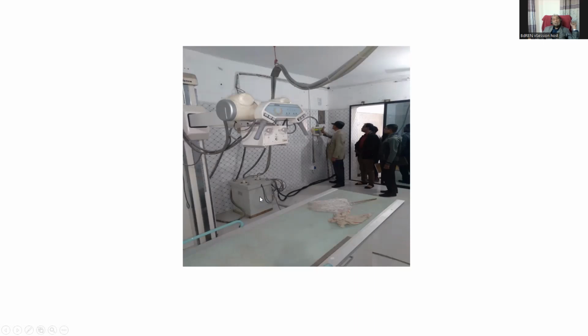For the performance of the X-ray, in this stand there is oil, an iron core, and several sophisticated components have been used. So it is known as the X-ray generator. Basically, it is a copper transformer. It transforms low voltage to high voltage. This is the state of the transformer. For example, our input is single phase, that is 220, for three phase 440, and this is the input voltage. And the output voltage for X-ray will be designed 40 to 125 kV or 150 kV DC voltage.